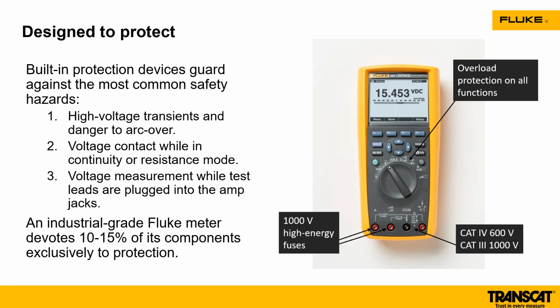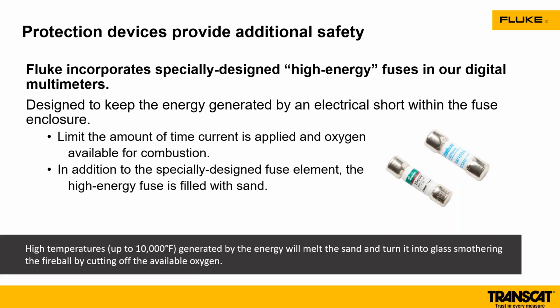It's solid metal, no resistance. That's where a fault could happen. So again, have the right meter for the right job. As it's mentioned here with fuses, make sure you put the right fuse in the meter as well. Use the fuse that's rated for this meter.